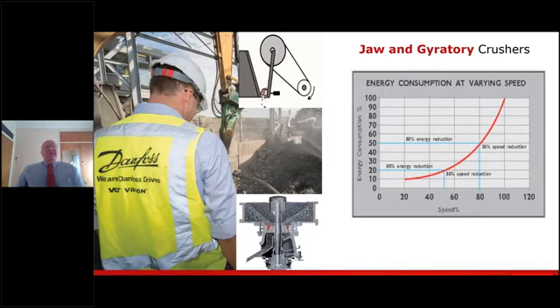So if we look at fixed versus variable speed control, the most common flow method is by means of a fixed speed motor, where the flow is adjusted by a mechanical device. And by using this technique, it doesn't only waste a tremendous amount of energy, it also actually wears out the equipment. Now, with the electrical variable speed drives, changing the flow is quite simply achieved by just adjusting the speed or the torque of the motor. And as somebody once said, it can actually be compared to taking your foot off the accelerator pedal of a car. Now, if you think about that, if you have your accelerator pedal pushed full down on your car, yes, the vehicle's moving fast at high speed.